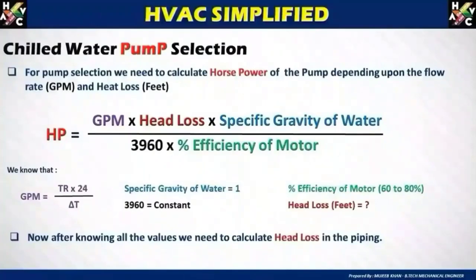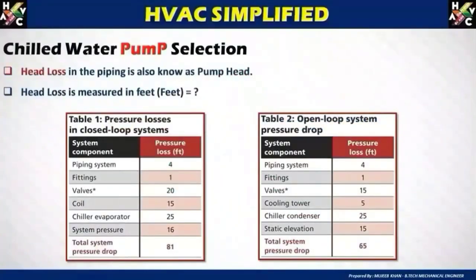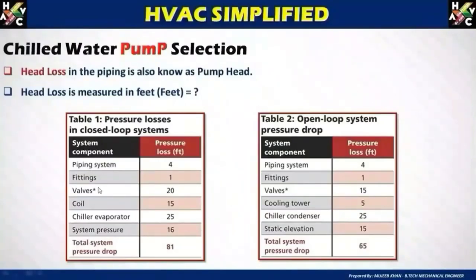Now I will show a simple example of an open loop system and a closed loop system — what parameters need to be calculated for head loss in the chilled water supply and return pipe. Head loss in the piping is also known as pump head, and is usually measured in feet, meters, and KPa. I have taken two examples in a table: table one covers pressure losses in a closed loop system, and table two covers open loop system pressure losses.